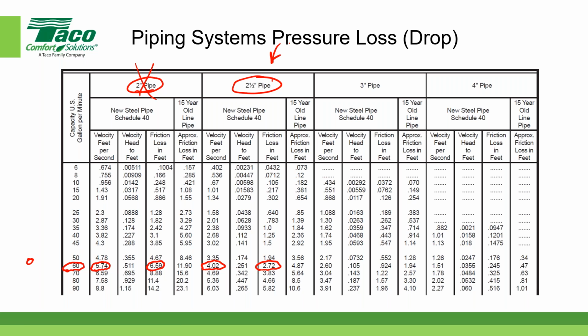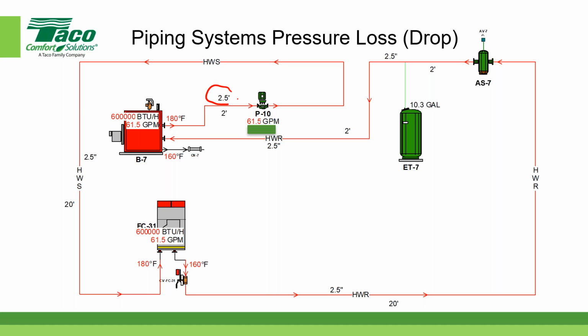So let's continue on. I've made my selection. It's 2.5-inch pipe. And now I want to number those points from point to point again. Let's see if I did this correctly in this diagram here. Look at that, it worked. And I got the same numbers that I wrote down manually. Pretty good. So I want to now create a little table, and I want to do the point-to-point calculation. I want to do the pressure drop from point to point. So for example, I have a piece of pipe that's connected to the discharge side of the boiler. That's point number 1. And then to the inlet of the pump, and I have a section of pipe. So let's say we put that in a table format here.